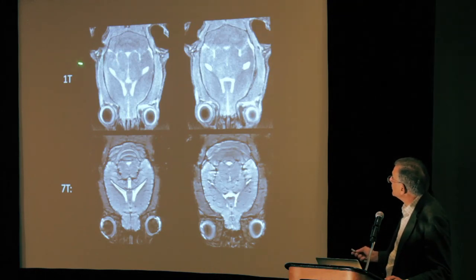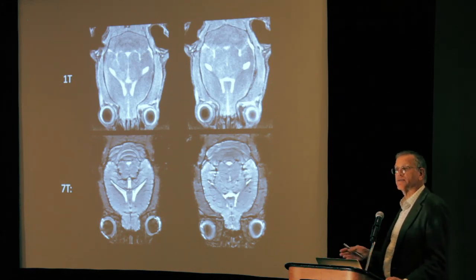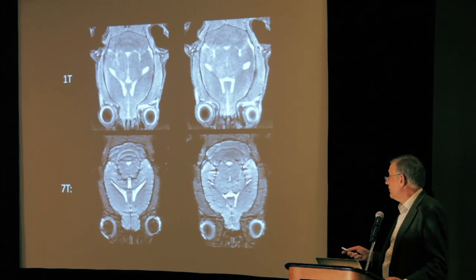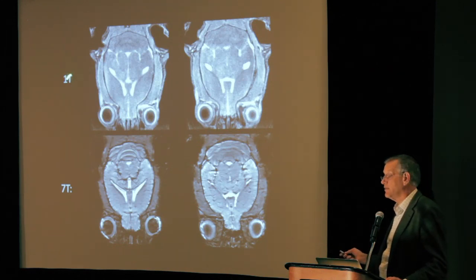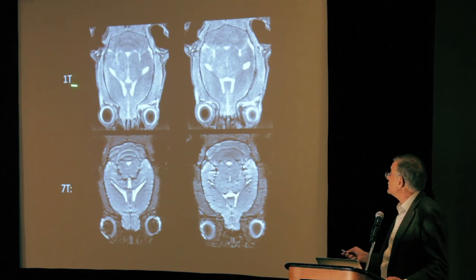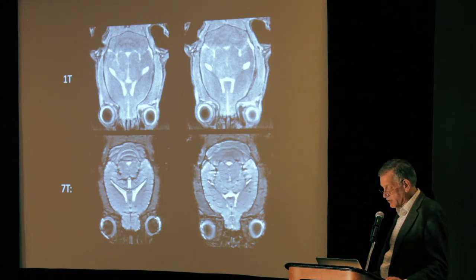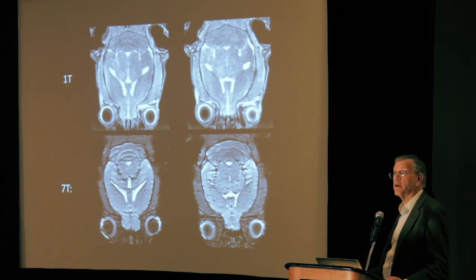This is a comparison of the animals done at 1 Tesla and at 7 Tesla. Not surprisingly, it's surprising to us initially, but in this case, we were actually pleased with the 1 Tesla images over the 7 Tesla because you can see here there's very little of the artifact. This is susceptibility artifact. Susceptibility artifact comes up and grabs you at higher and higher field. Now, to be fair, perhaps if we do some titration here with the 7 Tesla images, we can get to a point where we're not fighting the susceptibility artifact. But at this point, we are delighted with the results that we're getting here. It ain't broke, so we're not going to go ahead and fix it.